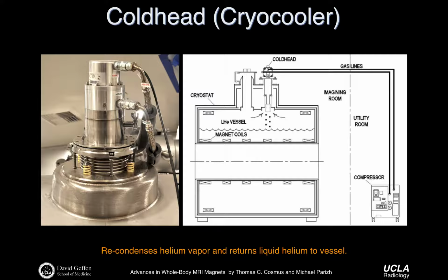If you walk into an MR suite, we'll do this for the labs, you hear this sort of chirping in the background. It usually goes, and that chirping is this compressor. There is helium inside that cryostat that will boil off ever so slightly. That can be captured and then recompressed and re-injected back into the system. And what that basically means is that while the system is trying to cool itself a little bit, this compressor is making sure we never have too little helium.